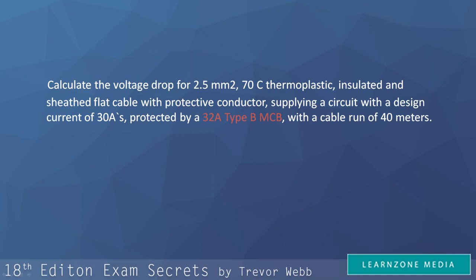Also, the question did not specify if the circuit was ring or radial, which in real life would be really important since you would not have a 32 amp MCB on a 2.5 mm squared radial circuit. This is why you should only pay attention to the data you need, such as the design current or the length of the circuit, and just ignore everything else. Try to remember this.